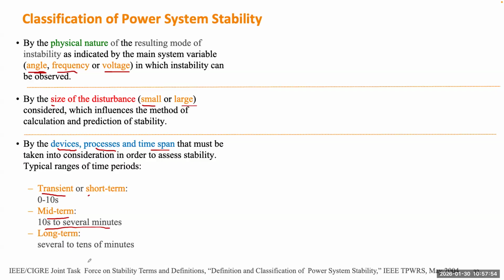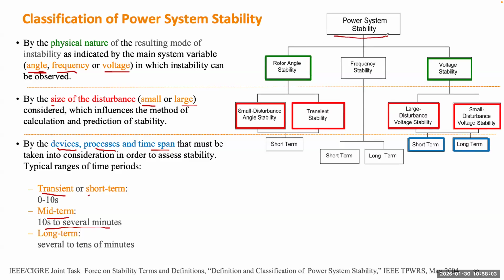Then let's use those three ideas to see how many specific stability problems we can generate. We start from power system stability as the integrated problem. From the first dimension, we study rotor angle stability, frequency stability, and voltage stability. In the second dimension, we consider small versus large disturbance. So we can have small disturbance angle stability, and large disturbance angle stability, which we typically call transient stability. Then we can have large disturbance voltage stability and small disturbance voltage stability. And from the time scale, we have either short-term or long-term. So we use three dimensions to finally create a number of highlighted boxes for specific measures or tools to solve.